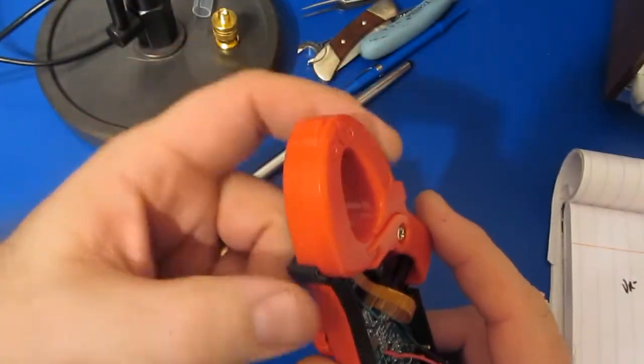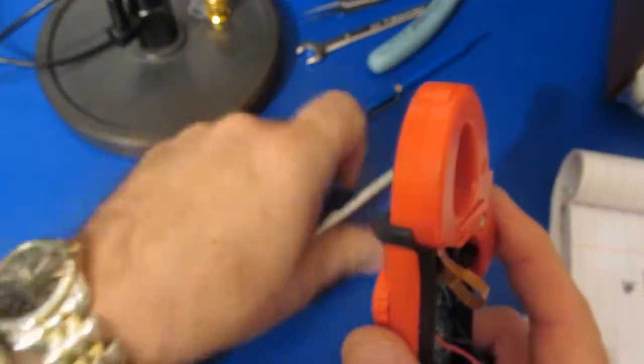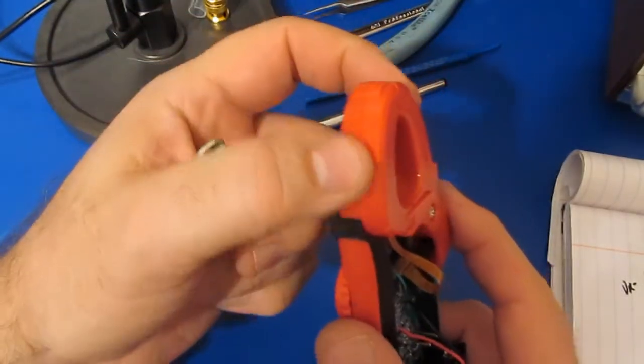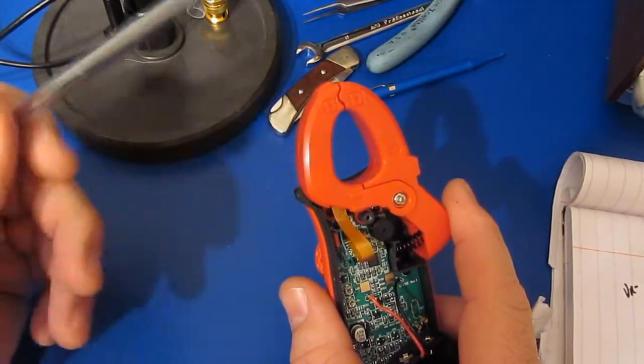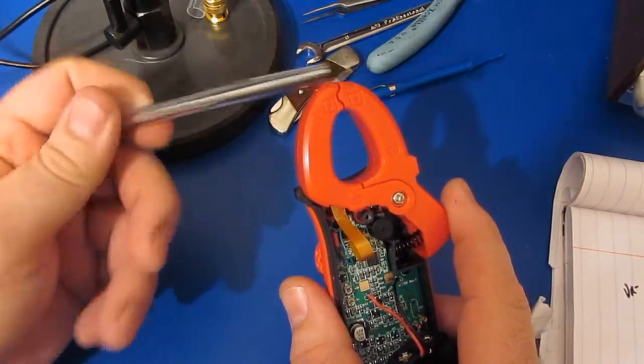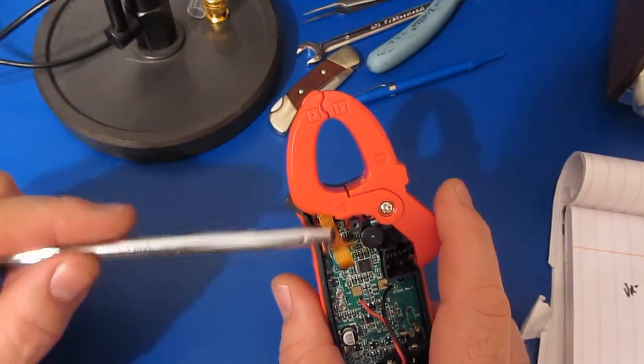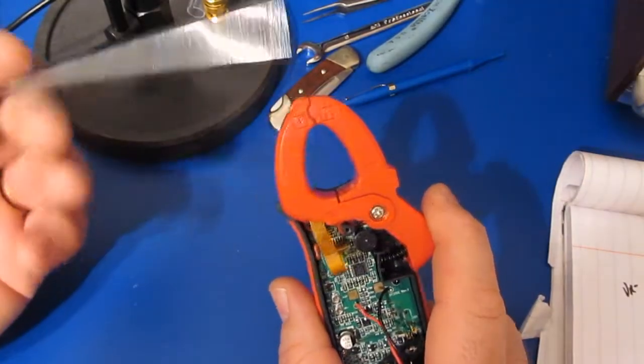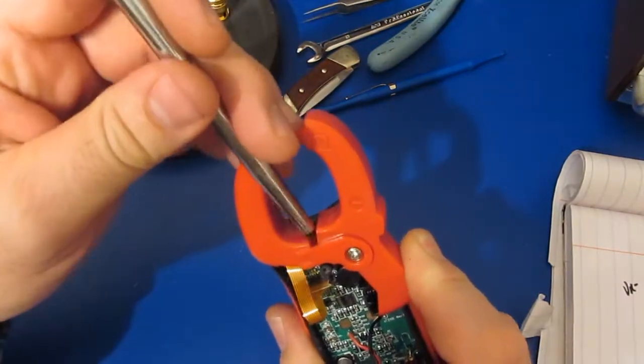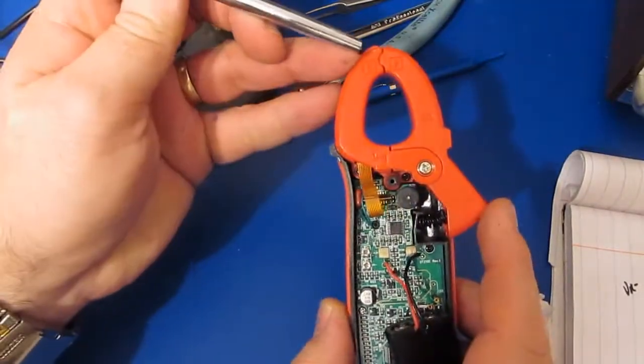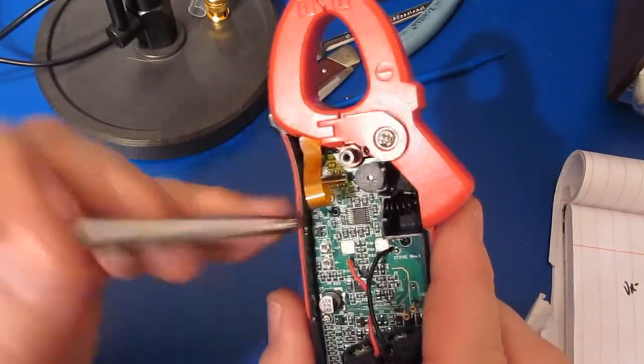The seams of the jaws here are actually glued together. I haven't seen anybody who's actually taken one of these apart. After I went ahead and removed the clamp section here, I took a small exacto knife and I went along the seam and I was able to break the glue joint around this. Each of these core halves is made up of what I would believe is a silicon steel laminate. So these laminates are stacked together like what you would see is a standard E-core transformer. So the cap down circuit board actually wraps around this half of the core. And then the sensors are located right at the two ends. These caps are actually pressed fit in. And these form the gap. Of course, they don't want this transformer to saturate. There's a small ground strap up in this area here and that just routes to this little green wire. And then again, this just routes back to the ground.